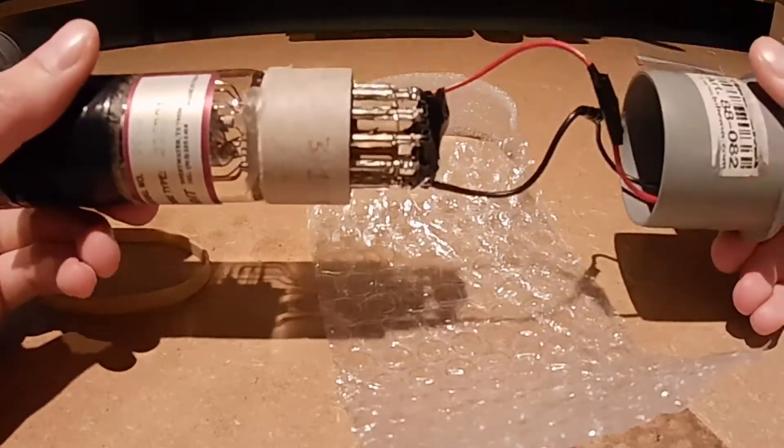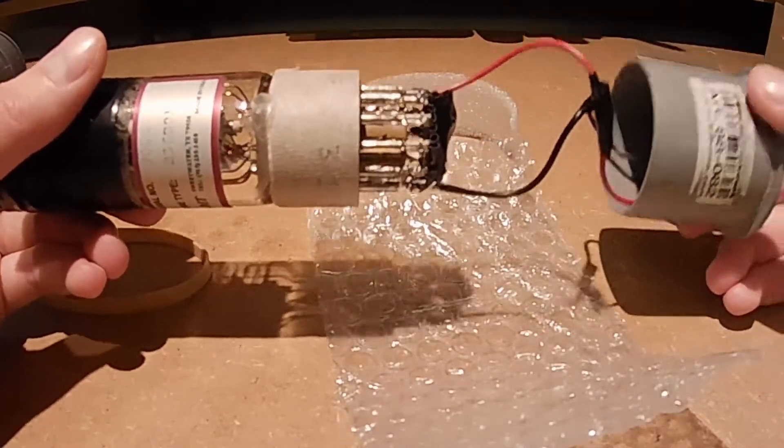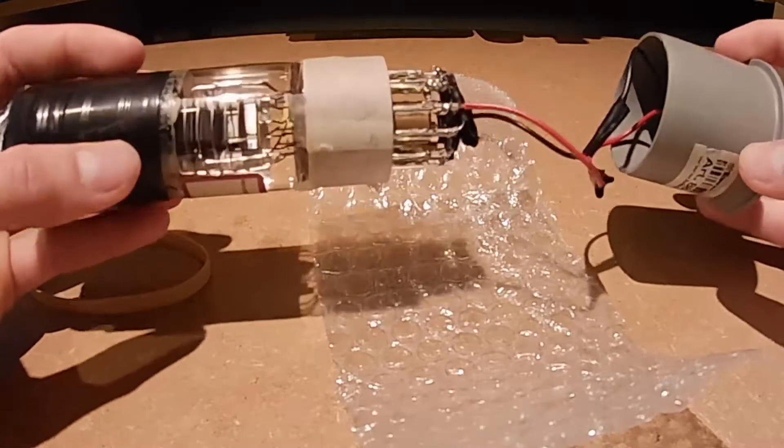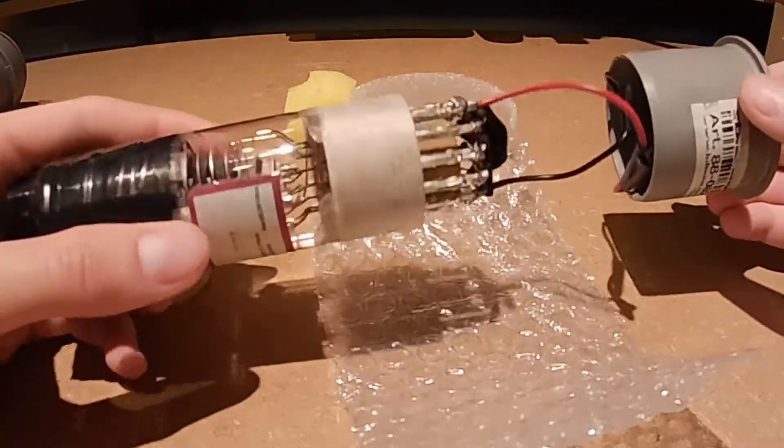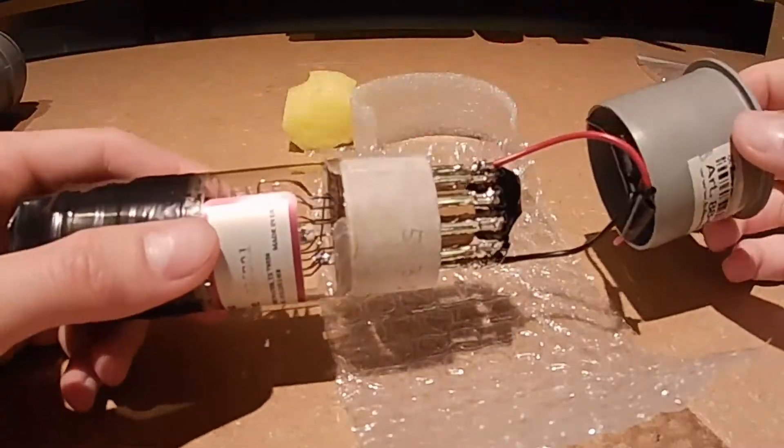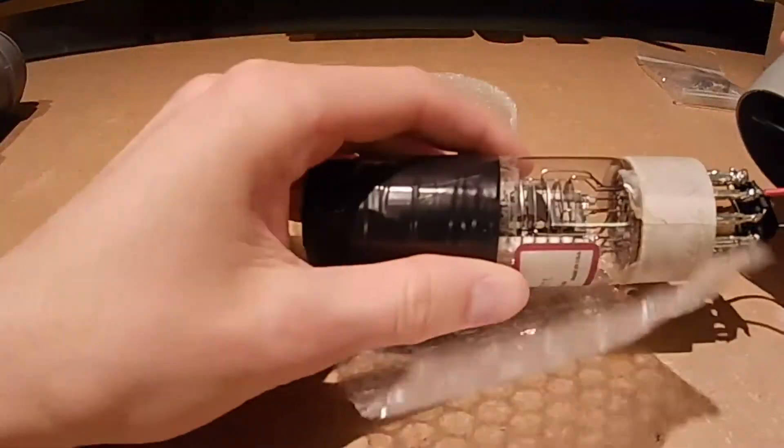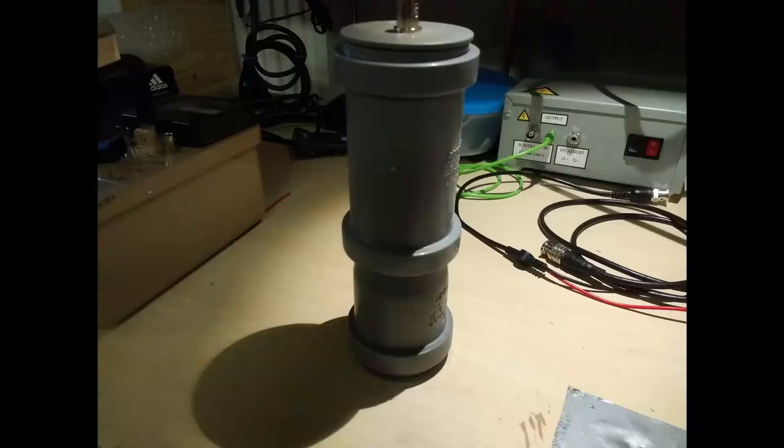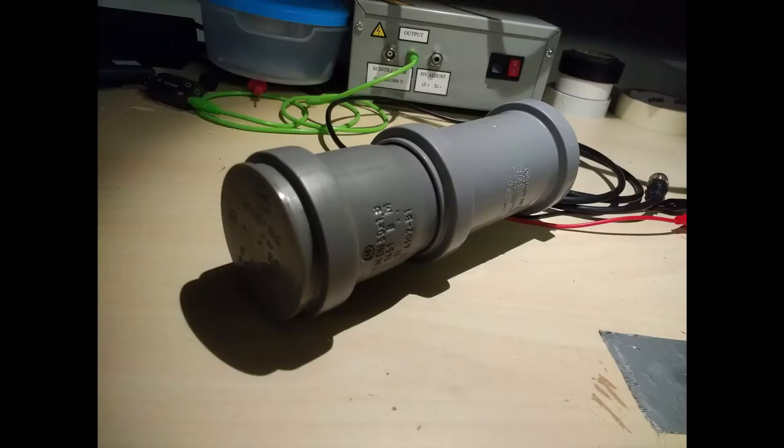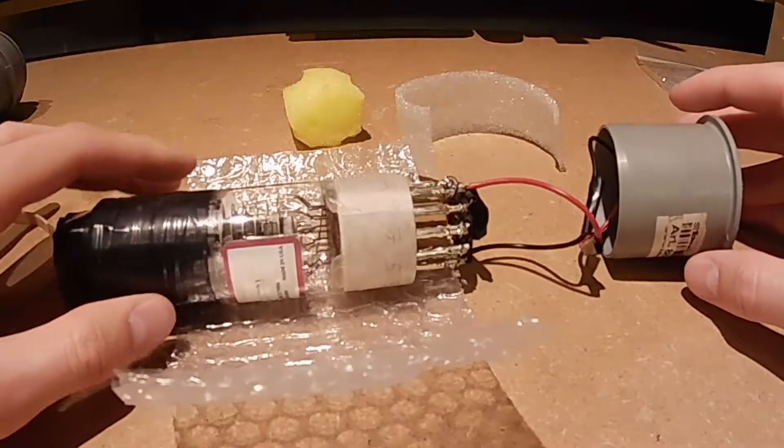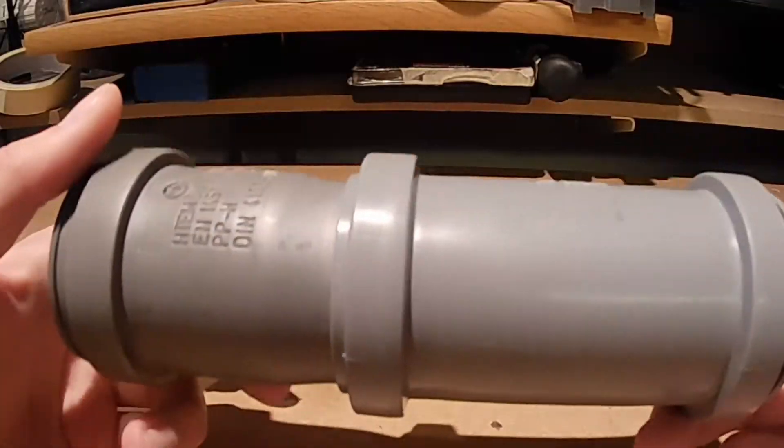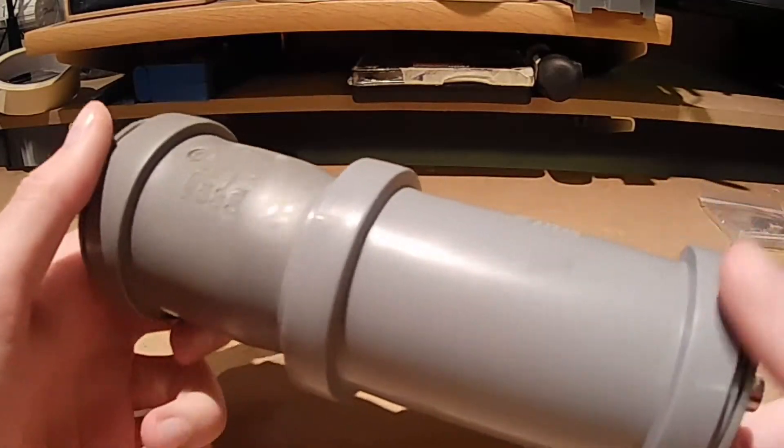Keep in mind that this is a positive high voltage wiring so it will only work with positive high voltage which is most rate meters. And put it in a light proof enclosure to block any light from hitting the photomultiplier tube. And that's pretty much all there is to it.